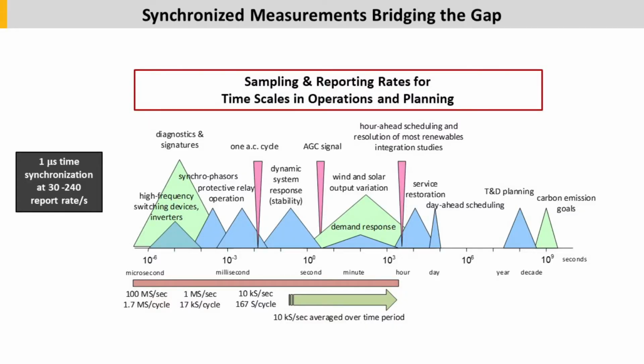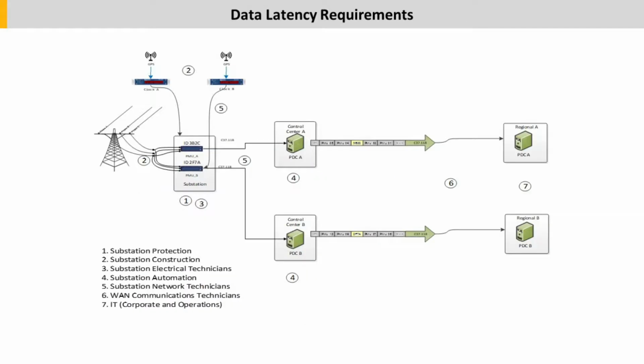Typical data delivery architectures at utilities are designed for SCADA data, where the measurements are polled. In the case of synchronized measurements, these data are published at a constant rate. Set up KPIs with your specific business units at the utility to ensure that this data arrives and is available with low latency, and that the availability statistics required for the applications are met.